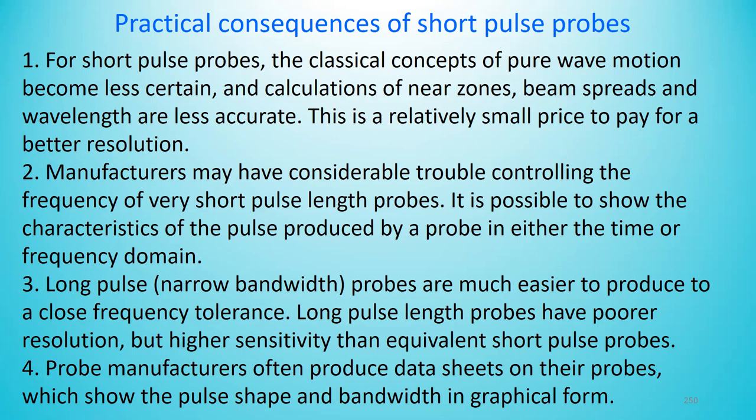It is possible to show the characteristics of the pulse produced by a probe in either the time or frequency domain. Long pulse, narrow bandwidth probes are much easier to produce with a close frequency tolerance. Long pulse length probes give poorer resolution but higher sensitivity than equivalent short pulse probes. Probe manufacturers often produce data sheets on their probes to show the pulse shape and bandwidth in graphical form.